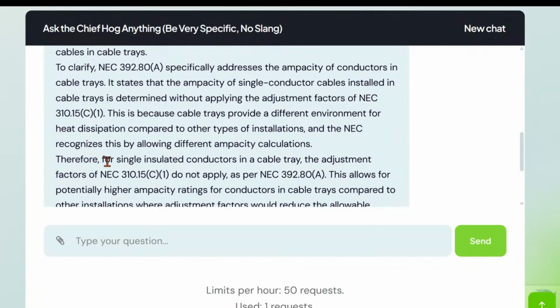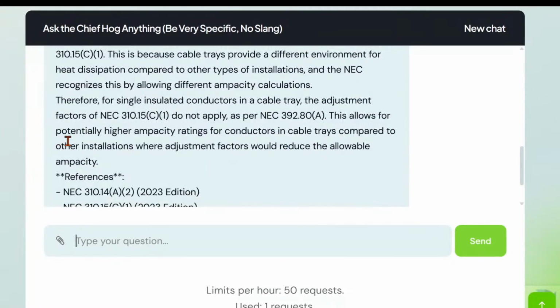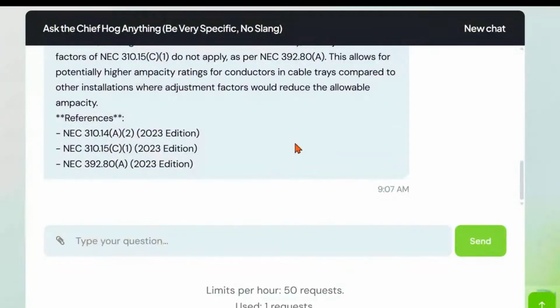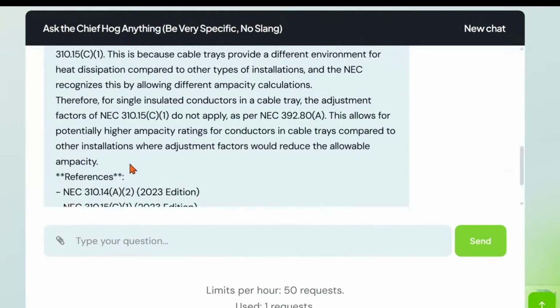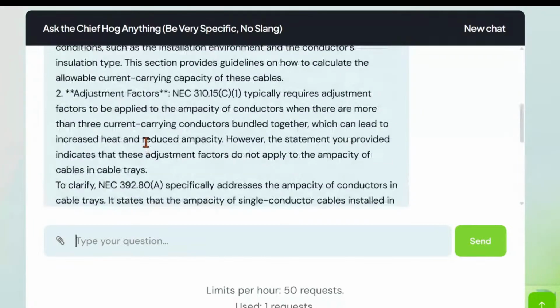Therefore, for single insulated conductors in a cable tray, the adjustment factors in 310.15(C)(1) do not apply, as per NEC 392.80(A). This allows for potential higher ampacity ratings for conductors in cable trays compared to other installations where adjustment factors would reduce the allowable ampacity. Wow, that's a lot, but this also is true, and it also gives you code references, right?